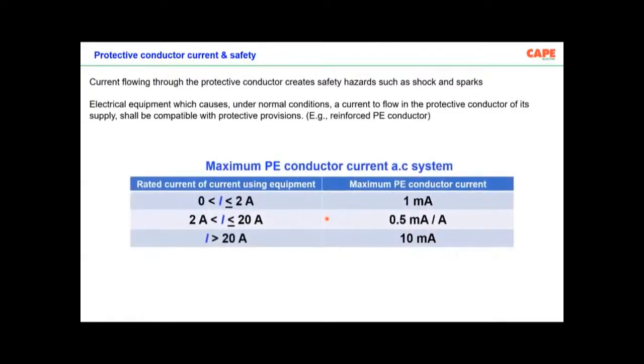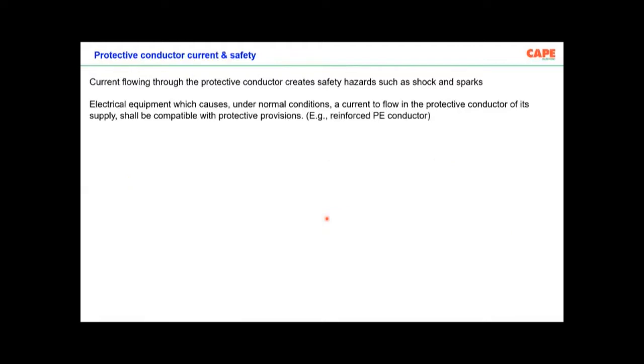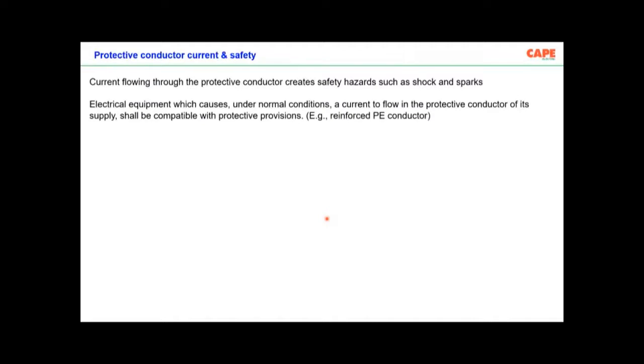Now, the next subject. So far I was explaining about the earthing, how you should make the earthing in an installation. The second part is what kind of wires or what kind of safety are required. Say, for example, protective conductor current. What is a protective conductor? A protective conductor is an earth wire. Different protective conductors are there, like PE conductor, PB conductor meaning protective bonding conductor, earthing conductor, and so on.